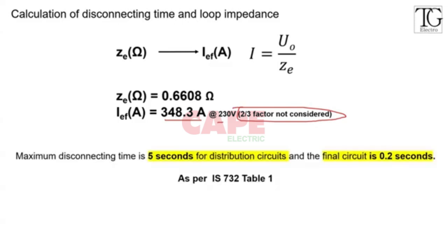Now, after getting this value, you have got the fault current at that location, and you have got the loop impedance of that location. But with this, you are also supposed to know that your protective device should trip at this fault current. So you have to make sure you select a good protective device. As per IS 732, the maximum disconnection time is 5 seconds for distribution circuits, and for final circuits it is 0.2 seconds.